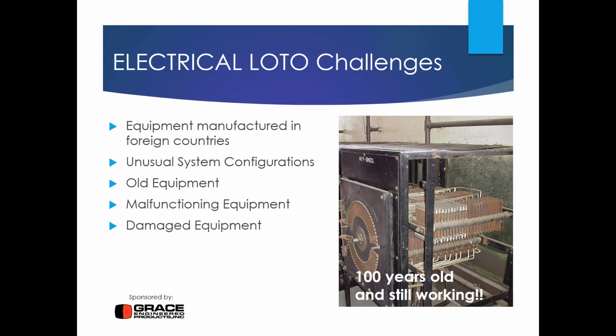Sometimes we have unusual configurations of systems. In older times, we used to have high voltage systems and low voltage systems in the same enclosure. There are also situations where some of the equipment is located at the back of an enclosure, which require you to get into an unsafe position to access that equipment. Of course, in those situations, what the 70E calls a special precautionary technique would be required. In other words, qualified workers have to be adept at not only doing things by the book, but they also have to know what to do when it won't fit normal by the book requirements.